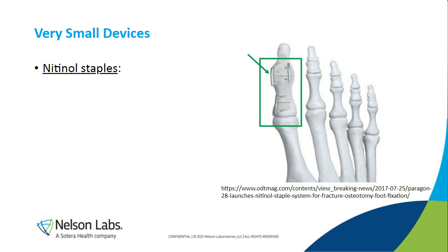So we had this example in-house where we have nitinol staples, and they're very small. For cytotoxicity tests, which require you to use a specific extraction ratio per the standard, we have to pull like 1 million of them together to get the required amount of extract for testing. In reality, however, we're not going to use 1 million of them on the patient because then you will turn into Robocop. But we need to understand that if something is really small, the way that the test is run or the test setup might not reflect the clinical situation, right? And if something is small, then it's really likely that that is the case. So always make sure that you take into consideration the way that the test was run.